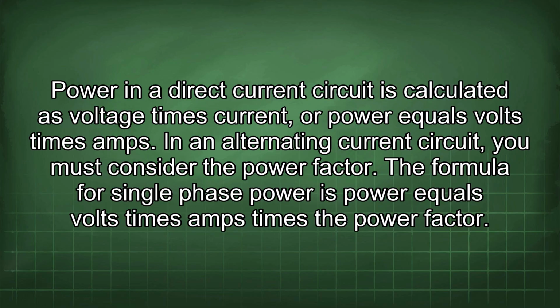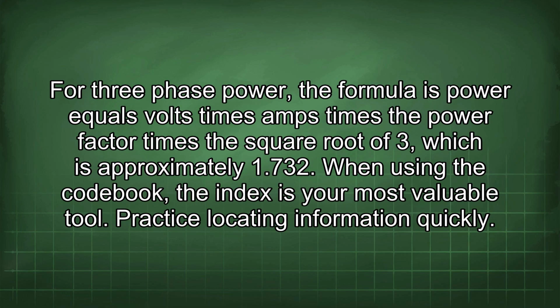Power in a direct current circuit is calculated as voltage times current, or power equals volts times amps. In an alternating current circuit, you must consider the power factor. The formula for single-phase power is power equals volts times amps times the power factor. For three-phase power, the formula is power equals volts times amps times the power factor times the square root of 3, which is approximately 1.732.